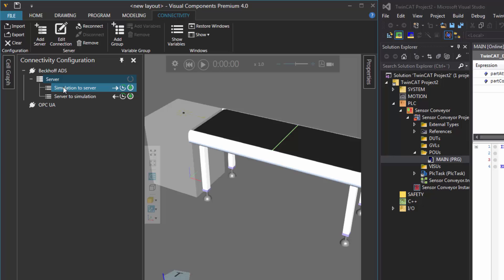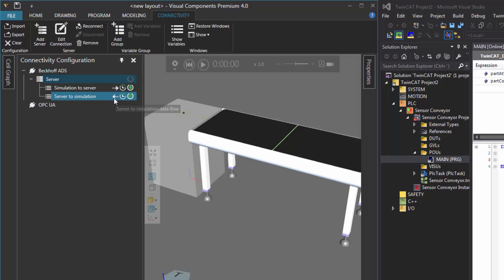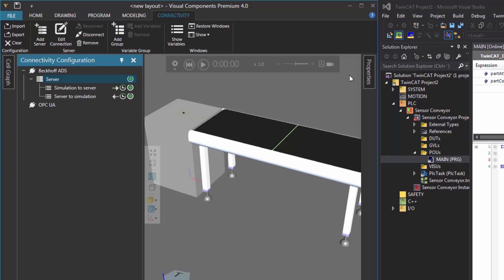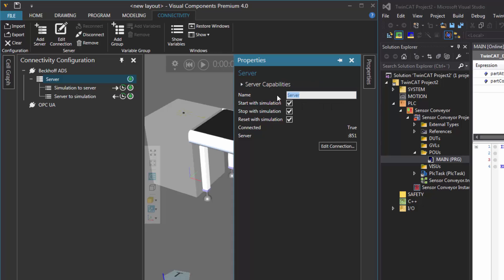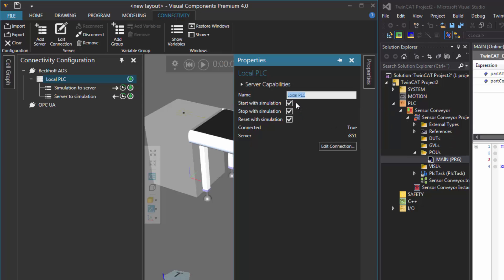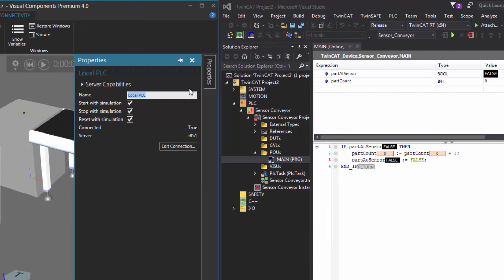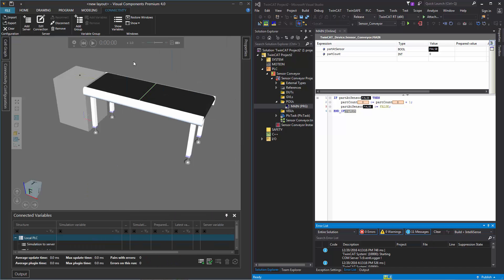Notice there's a connection and we have these variable groups. 'Simulation to server' — the arrow indicates the direction of data flow, so variables in your simulation can set the values of variables in your PLC. And 'server to simulation' — variables in your PLC can set the values of variables in your simulation. Right now this connection is not active, so I'll click the button to connect to it. In the properties panel, let's rename this connection to 'local PLC'. Its connected property is now set to true and it's listening to port 851. You also have settings so that when you start your simulation you can start the PLC program, and when you stop or reset it you can control that from your simulation controls as well.